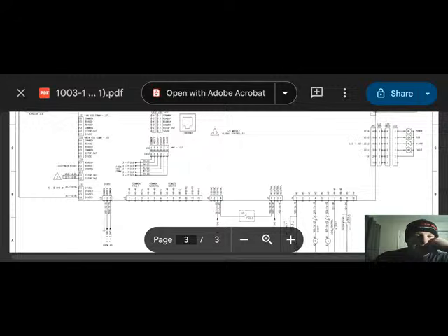Again, just make sure these are usually rated like 250 volts or something, so it's pretty tough to exceed them. So if you're just running like a standard 120-volt circuit or even a 24-volt circuit, you're going to be just fine. Common warning works kind of the same way. It's just that what's going to trigger these is, you get a service warning, or you get the warning before it trips out on high temperature. This is a set of contacts that's going to activate when your machine actually goes into a fault.